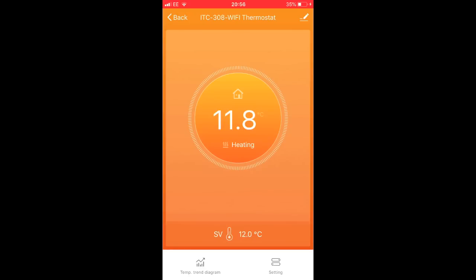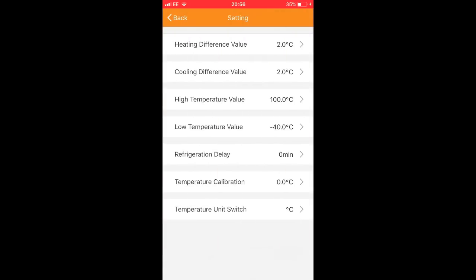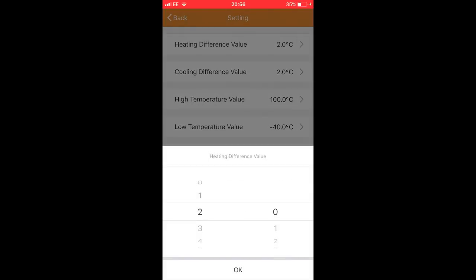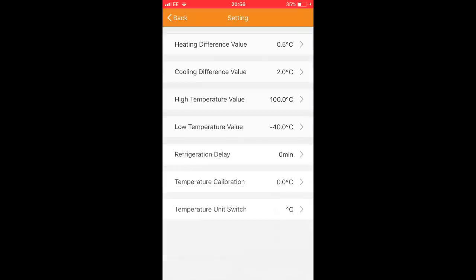Now we want to go in and check some of the other settings we've got here. The heating and cooling difference values are 2 degrees, which is higher than I want at the moment, so I'm going to put both of those to 0.5.